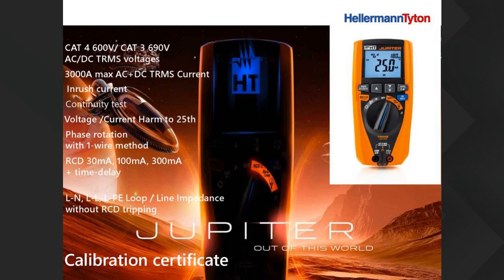So this will give you a time delay and say to you, okay, no, it took, let's say, 500 milliseconds. So 500 milliseconds is already far too long. So by default, it's better to replace that earth leakage and not use it anymore. Then the meter, when it can do your prospective short circuit current and loop tripping as well.